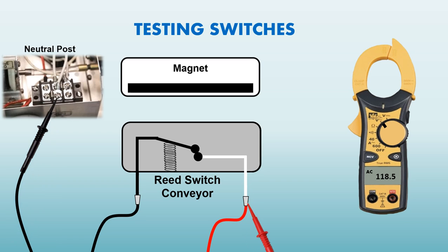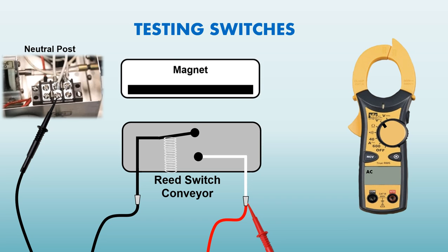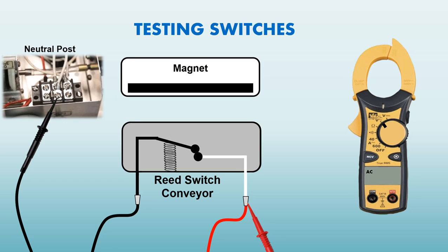Let's take a look at one more example of a reed switch. This would be the example of a reed switch that's on a conveyor. When testing a reed switch, we would attach the meter lead to the discharge side of the reed switch and to a common. It would show that the switch is closed. This is when the magnet has been removed. Remember, on a conveyor, when you put a rack in, it activates the sequence bar and it removes the magnet from atop the reed switch. That allows the switch to go to its normal resting position and the switch will close.